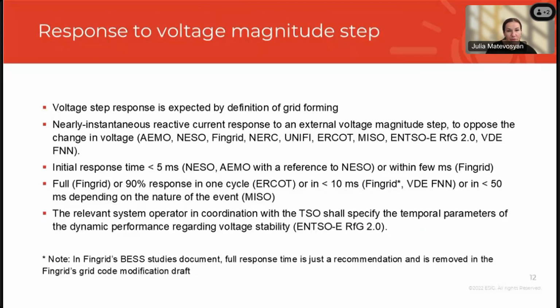So in response to voltage magnitude step, again, this is by definition of grid forming. The expectation is that there is nearly instantaneous reactive current response to external voltage magnitude step to oppose the change in voltage. And it's basically the same across all of the requirements. It doesn't use exactly the same language, but that's what the requirement is, pretty much the same.